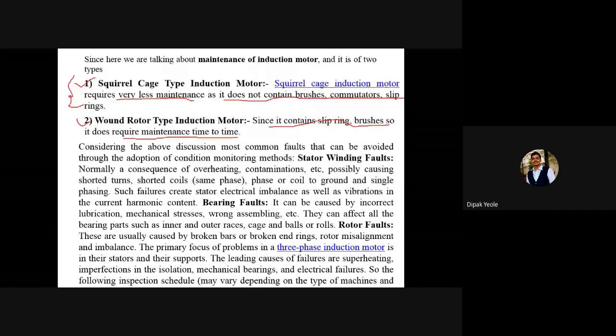Considering the above discussion, the most common faults that can be avoided through adoption of condition monitoring methods are called stator winding faults. These are normally a consequence of overheating and contamination, possibly causing shorted turns, shorted coils, phase or coil to ground, and single phasing.